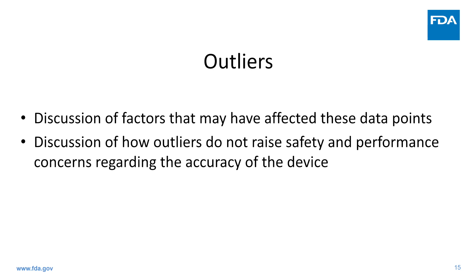So, what are some of the questions that the agency has about the clinical desaturation studies as they are currently received? Given the limitations and purposes of pre-market desaturation testing, it is important to consider the following questions. Currently, pulse oximeters are not diagnostic medical devices. Instead, they are verified to be estimates of SpO2 within 2 ARMS for 95% of the data pairs. In this function, they are tools, and interpretation and verification of the SpO2 is particularly relegated to the clinician or the learned intermediary looking at the signal and values. In the current indication, adequate for clinical decision making, these are some of the questions we have.